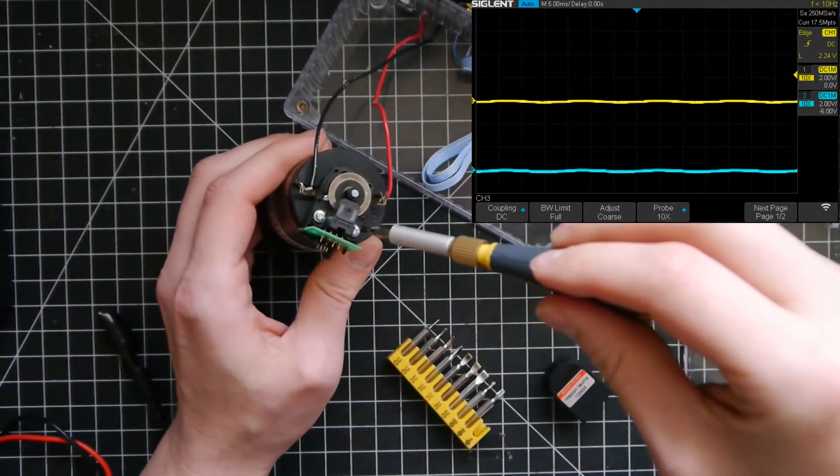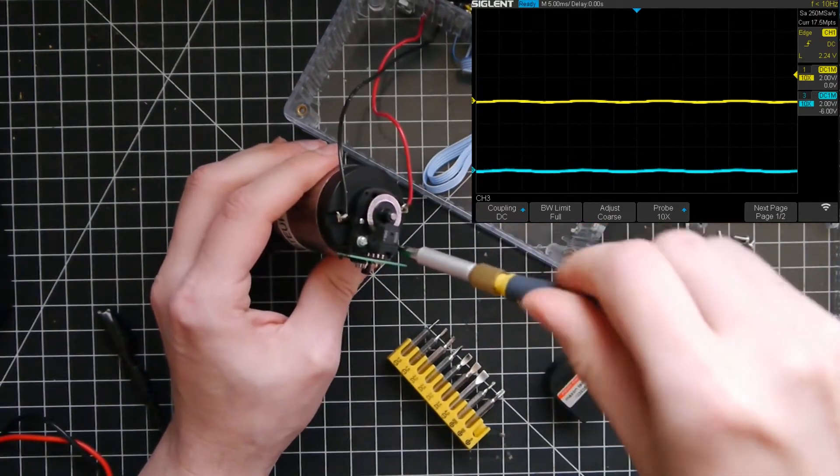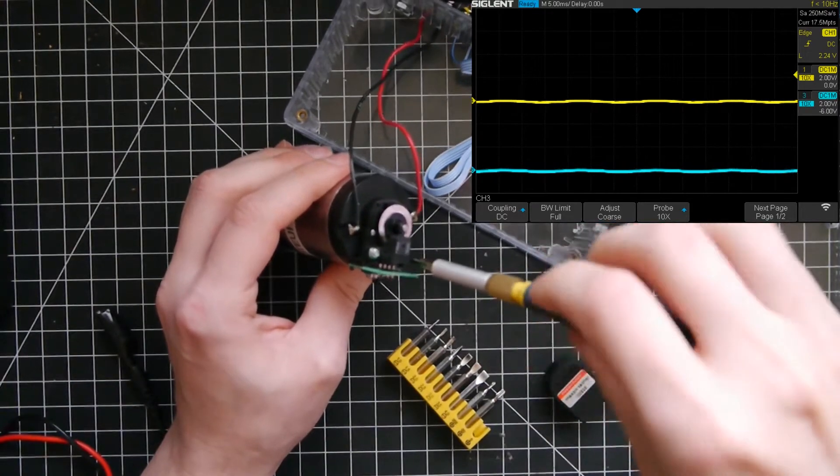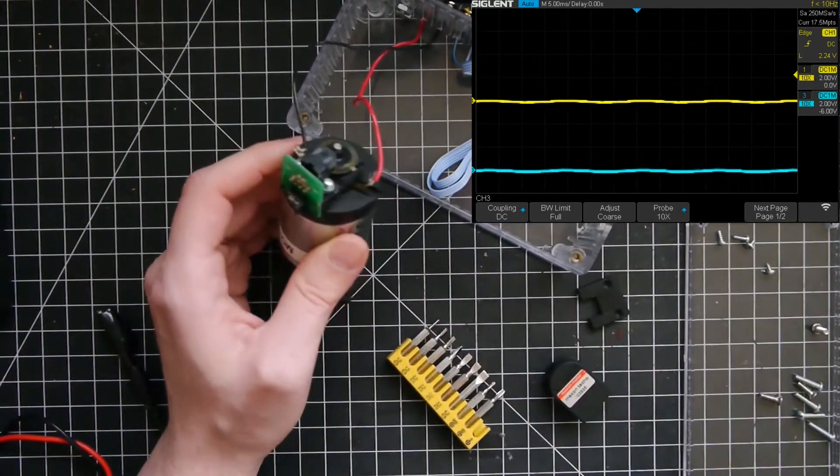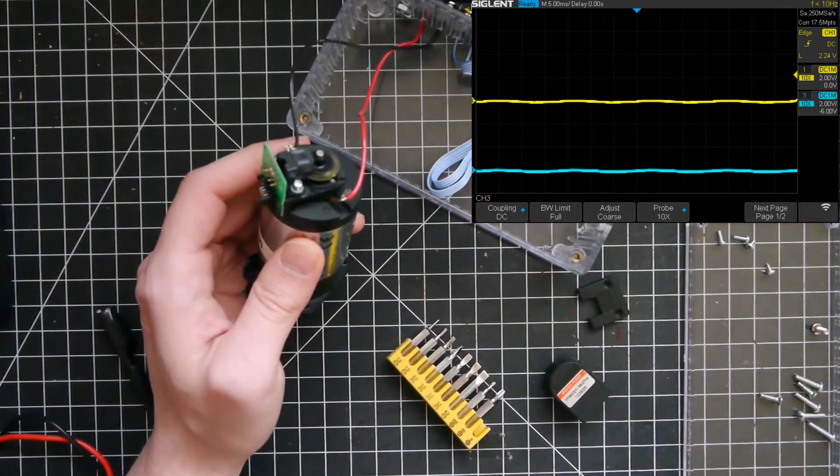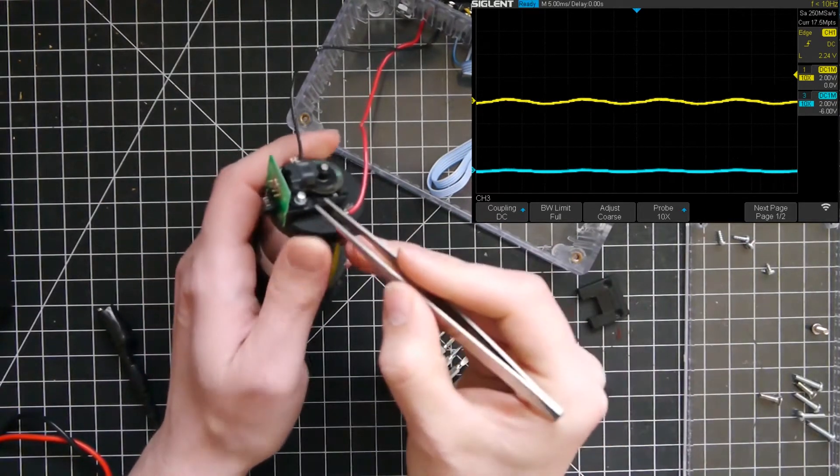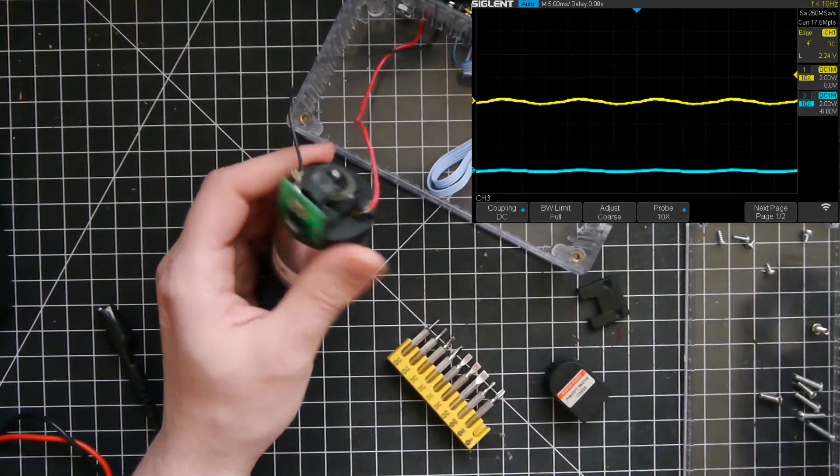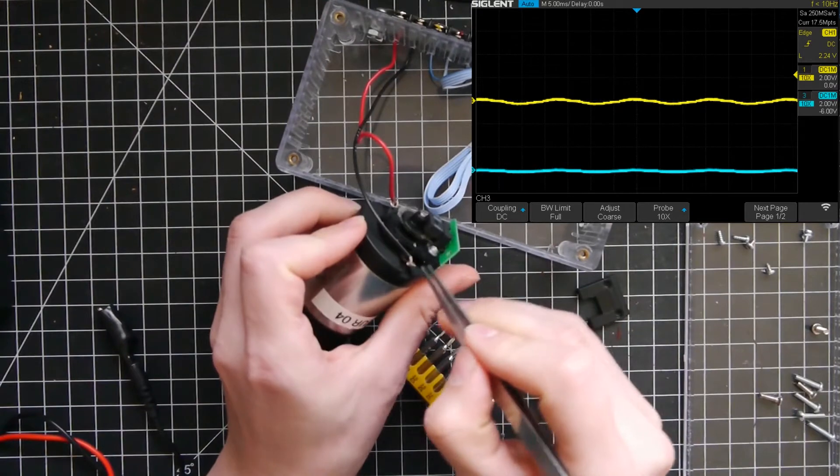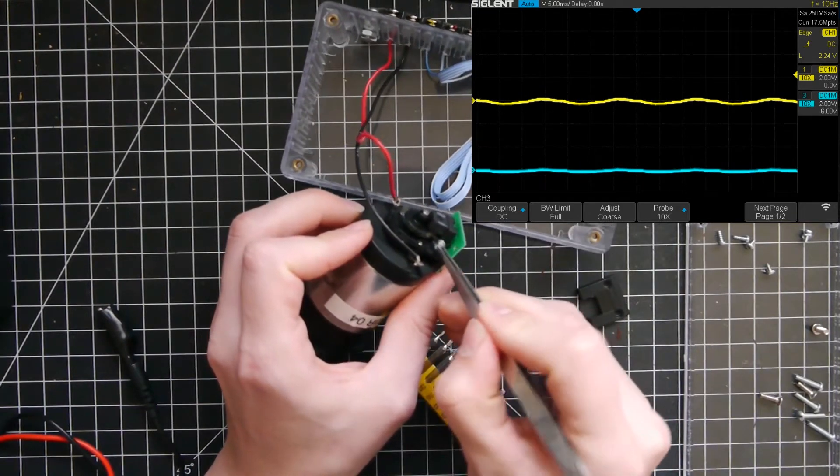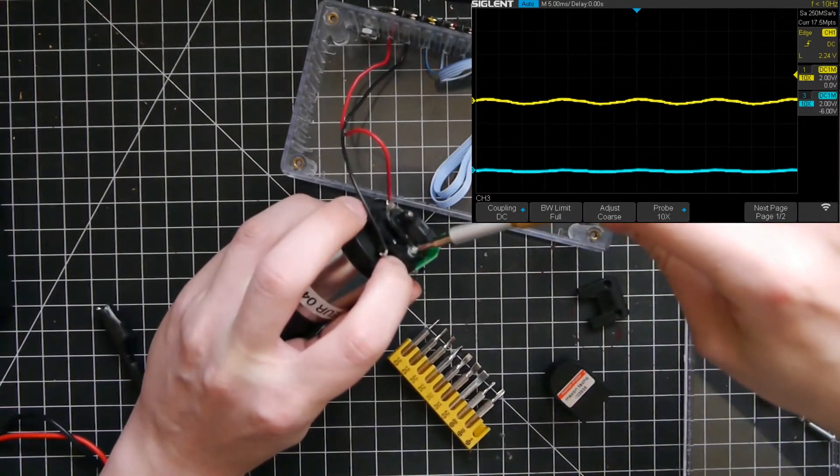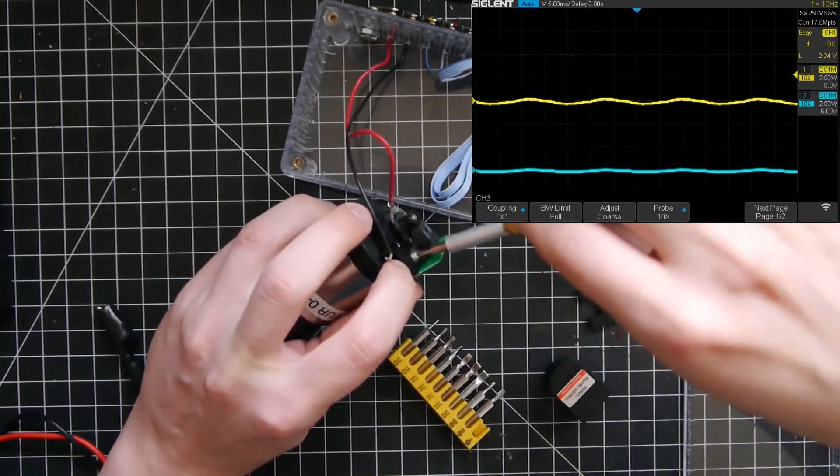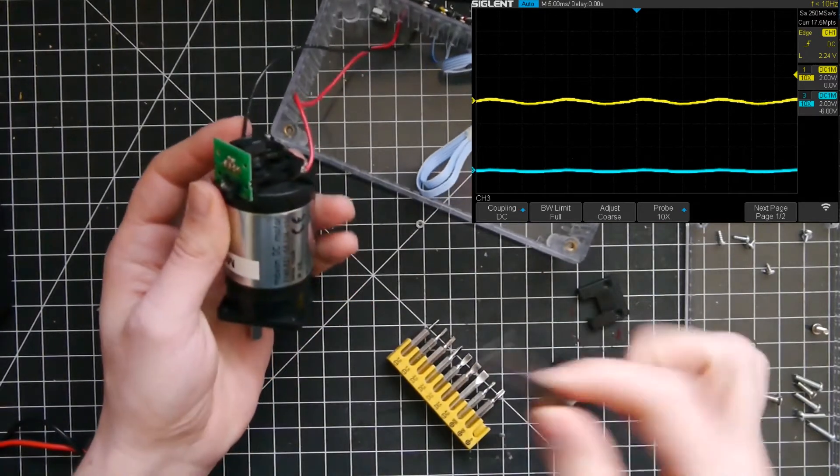I continue my disassembly, I will now remove the main circuit that includes all the components required for the interpretation of the optical signal, namely the phototransistors and the light emitter, typically an infrared LED. And since there seems to be no mechanical damage on the encoder, it is probably this circuit that is no longer working. Therefore, the logical thing we have to do here is to change this circuit and see if it solves our problem.